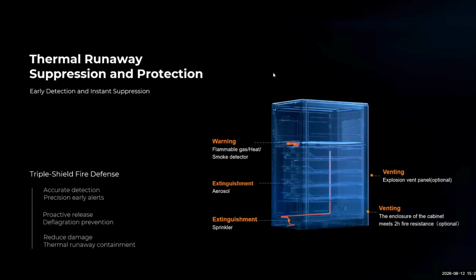Besides the detectors, the built-in fire extinguisher module uses aerosol. When the internal temperature is more than 90 degrees, it will activate to release aerosol to cool down all the battery modules and prevent any fire from spreading. There are also optional functions for the sprinkler and explosion venting panels. The whole cabinet materials can also prevent fire for up to 2 hours.